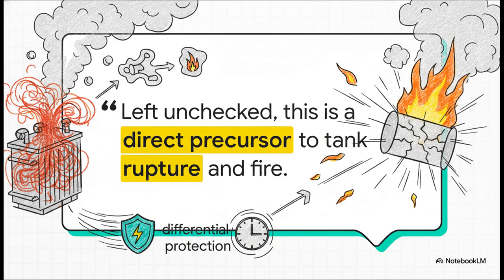That intense, localized heat will vaporize the insulating oil inside the transformer. This generates highly combustible gases. Left unchecked for even a fraction of a second too long, you aren't just looking at a broken transformer, you are looking at a direct precursor to a massive tank rupture and fire. That is exactly why the blazing speed of differential protection is mandatory.